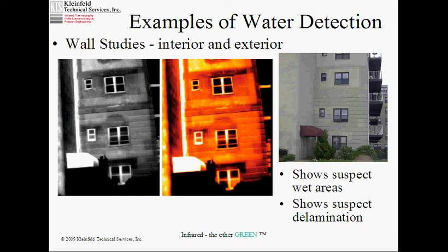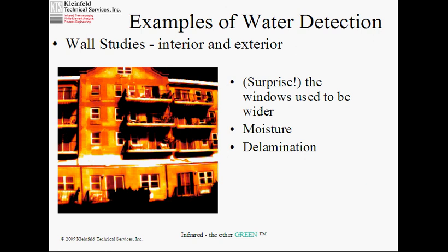So it's a much longer flow path than straight through as it is in the areas next to it. That means that this area can't absorb the heat, can't get rid of the heat as quickly, as readily as the other areas, and it gets hot under an applied load. Similarly at night, the building is not feeding it, so it actually cools off faster. And I'm going to show you some graphs that explain this.